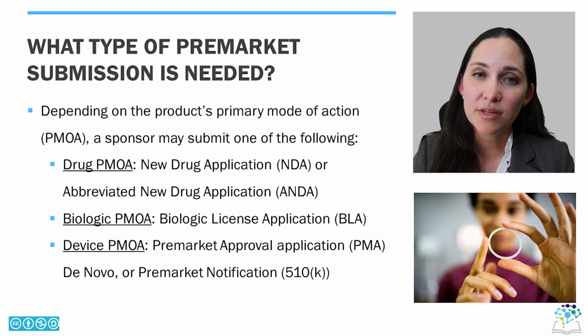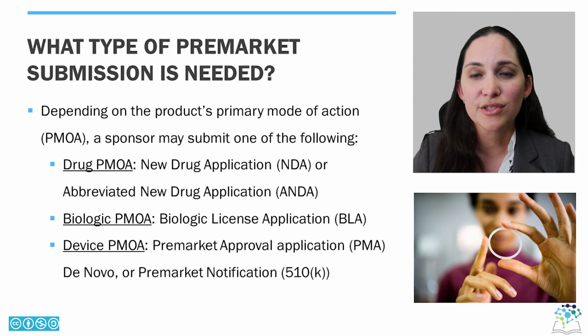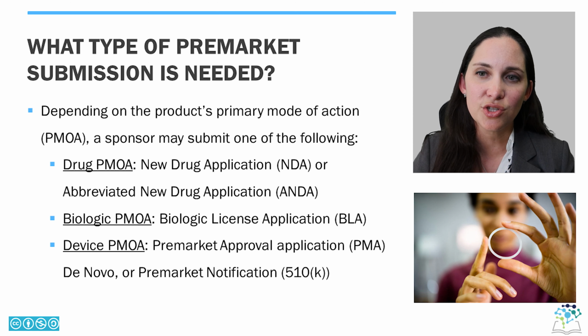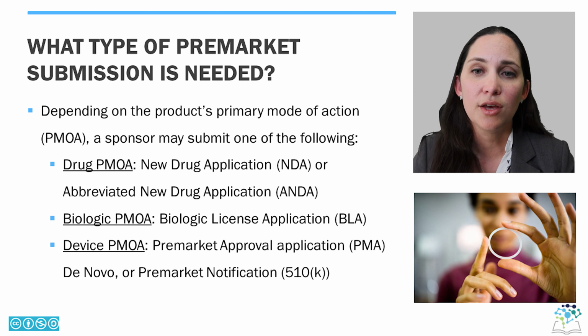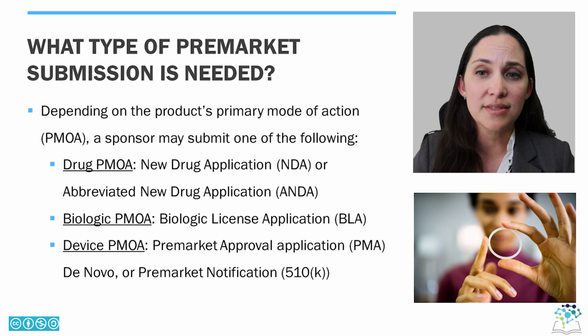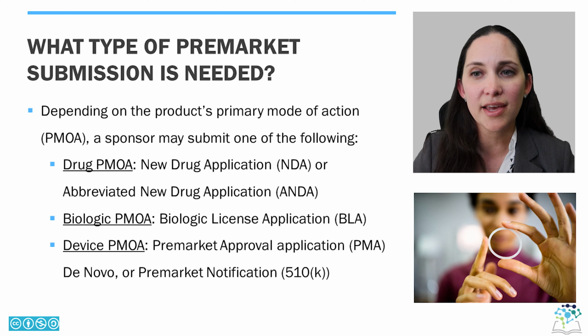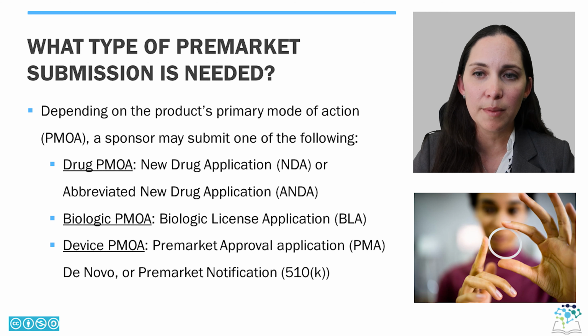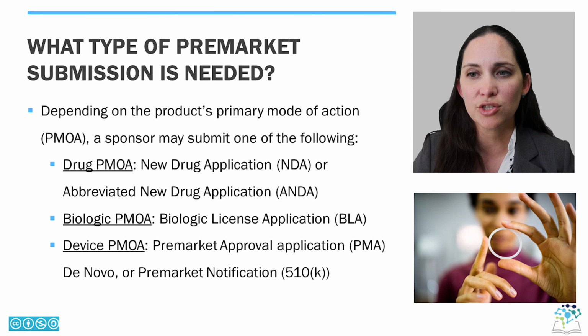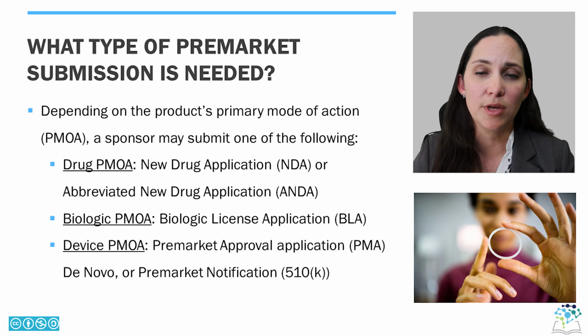Next, what type of premarket submission is needed? Combination products are typically marketed under a marketing authorization type associated with the constituent part that provides the PMOA for the combination product. For example, depending on the PMOA, a sponsor may submit one of the following: either a new drug application, or NDA, or an abbreviated new drug application, ANDA, for a drug PMOA; a biologic license application, or BLA, for a biologic PMOA; and finally a premarket approval application, or PMA, de novo, or premarket notification known as the 510(k) if you have a device PMOA.